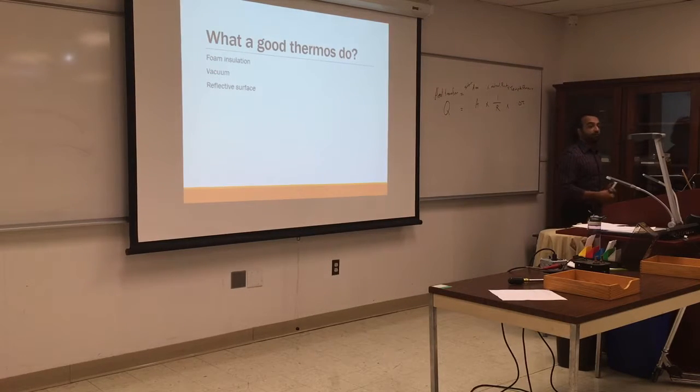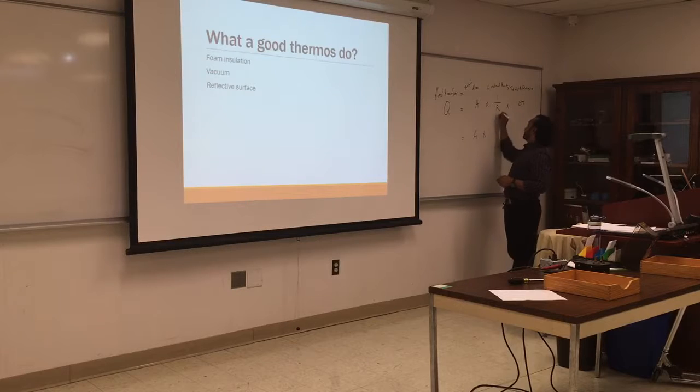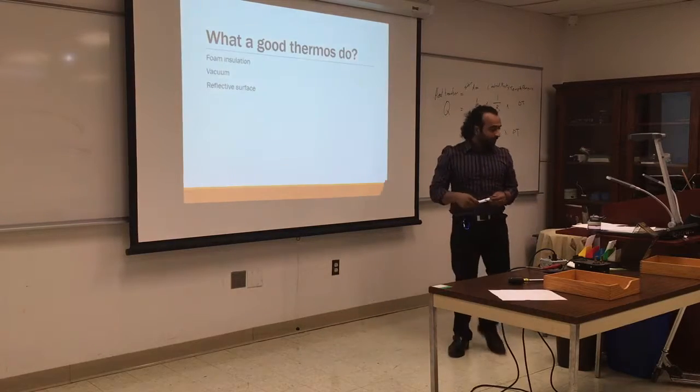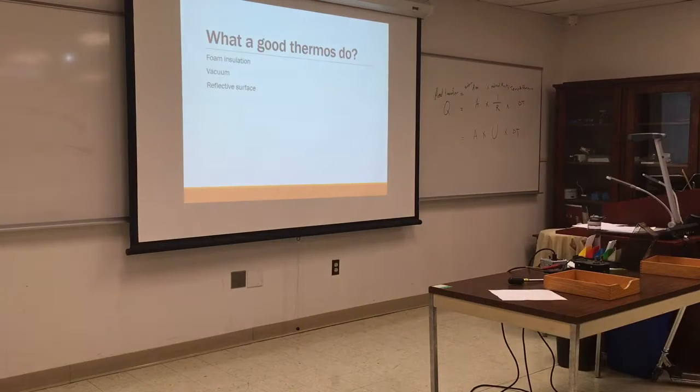To make things easier for us technicians, you might go and find something called U. Because people do not like to see 1 over R, it's confusing. So they just give you the U factor, which is 1 over R. If you look at your heat loss book, you look at the back, they give you the U factor. Nobody wants to look at reciprocals and inverse.